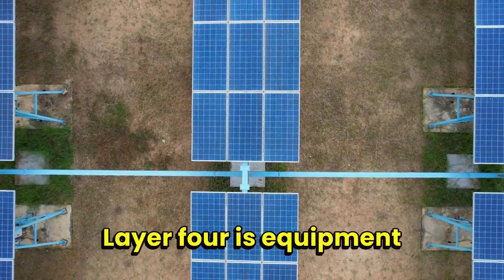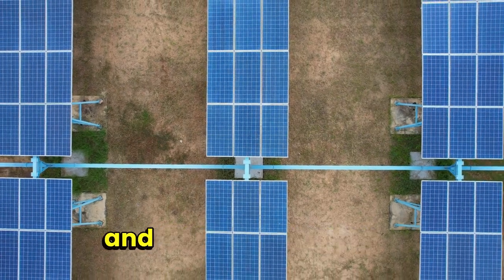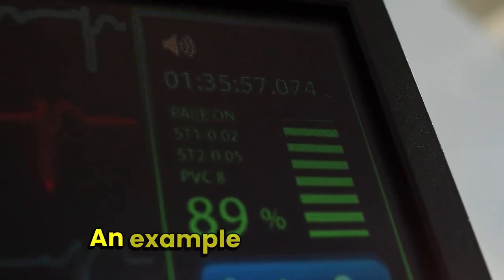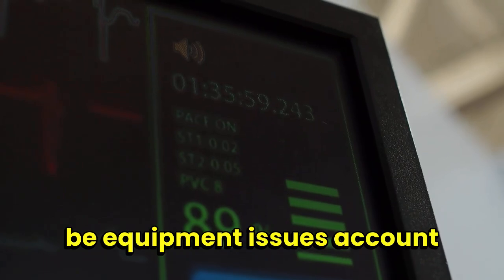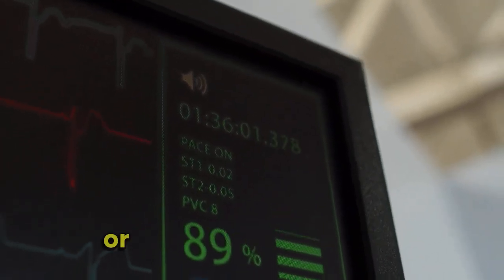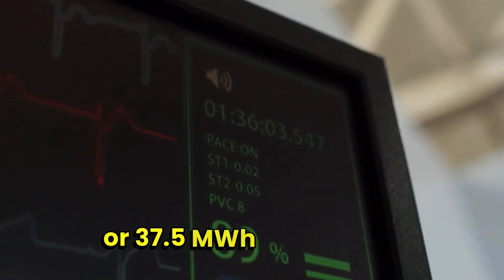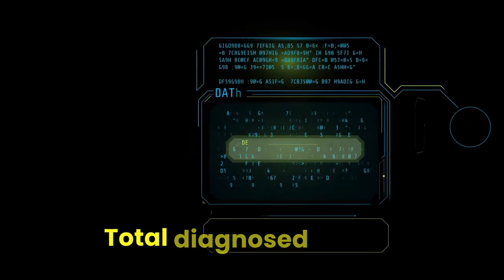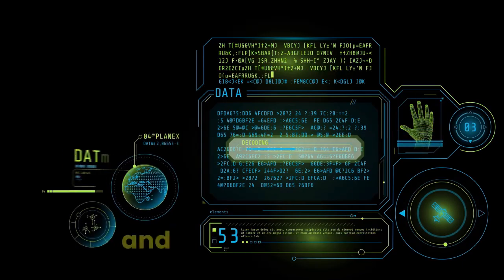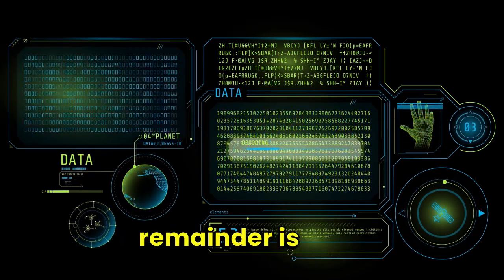Layer 4 is equipment failures identified by thermal imaging and SCADA correlation. An example output would be equipment issues account for 0.3% loss, or 37.5 MWh per month. Total diagnosed equals the 4% loss, and the unexplained remainder is zero.